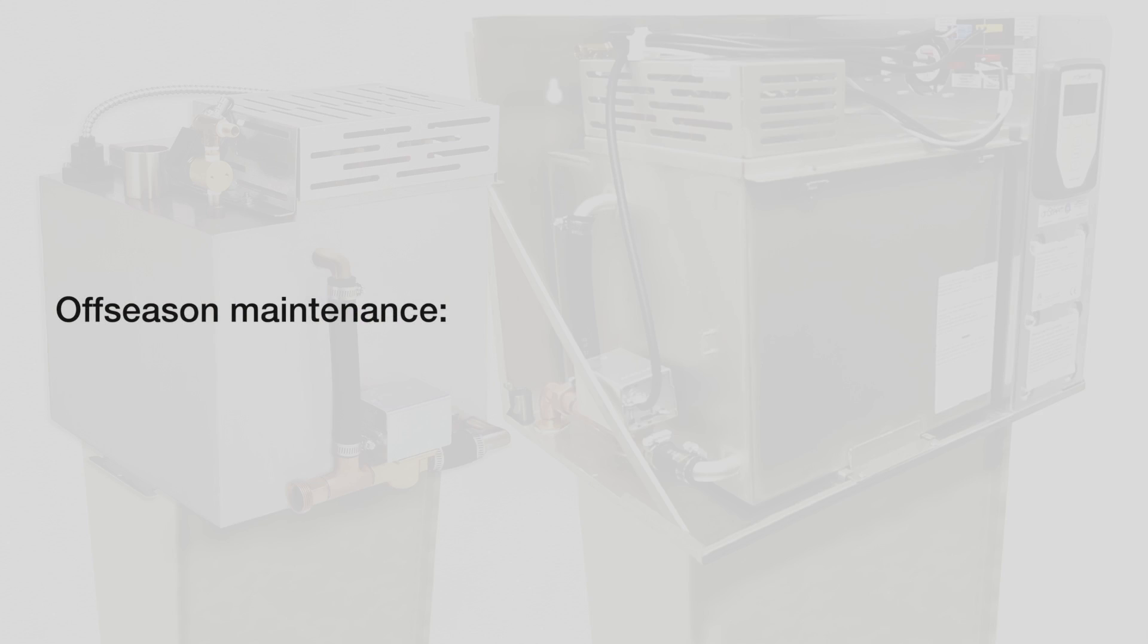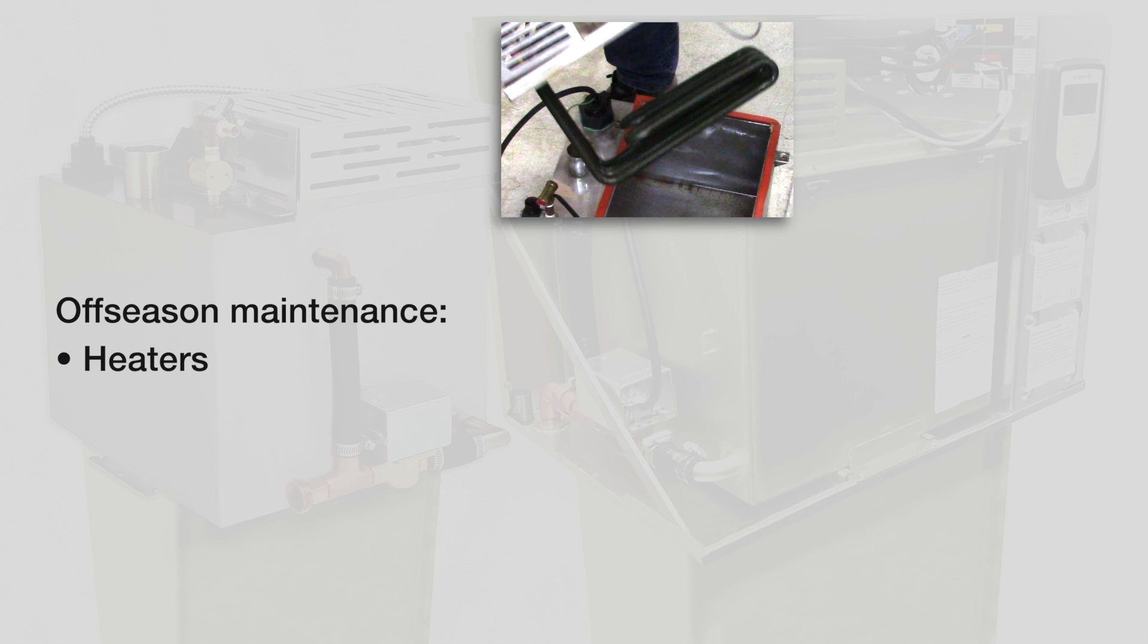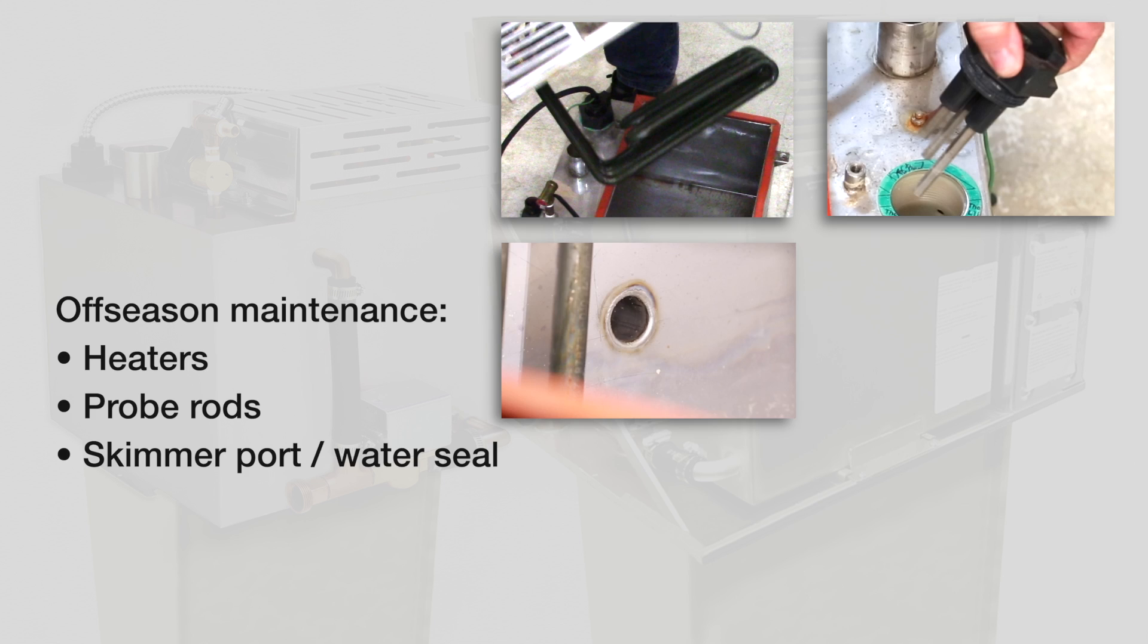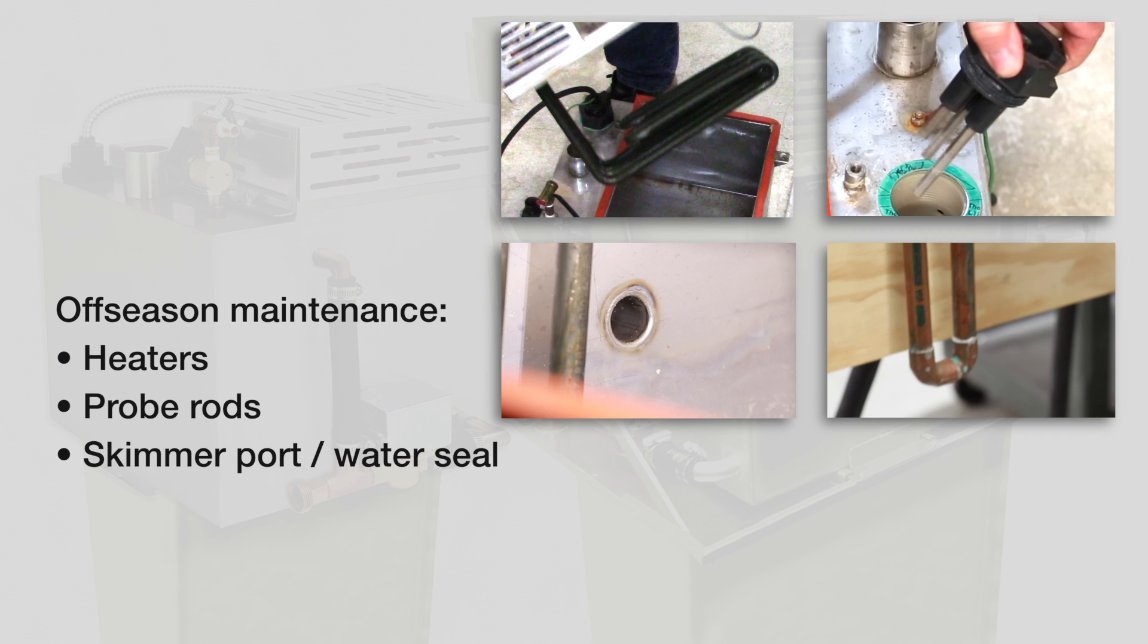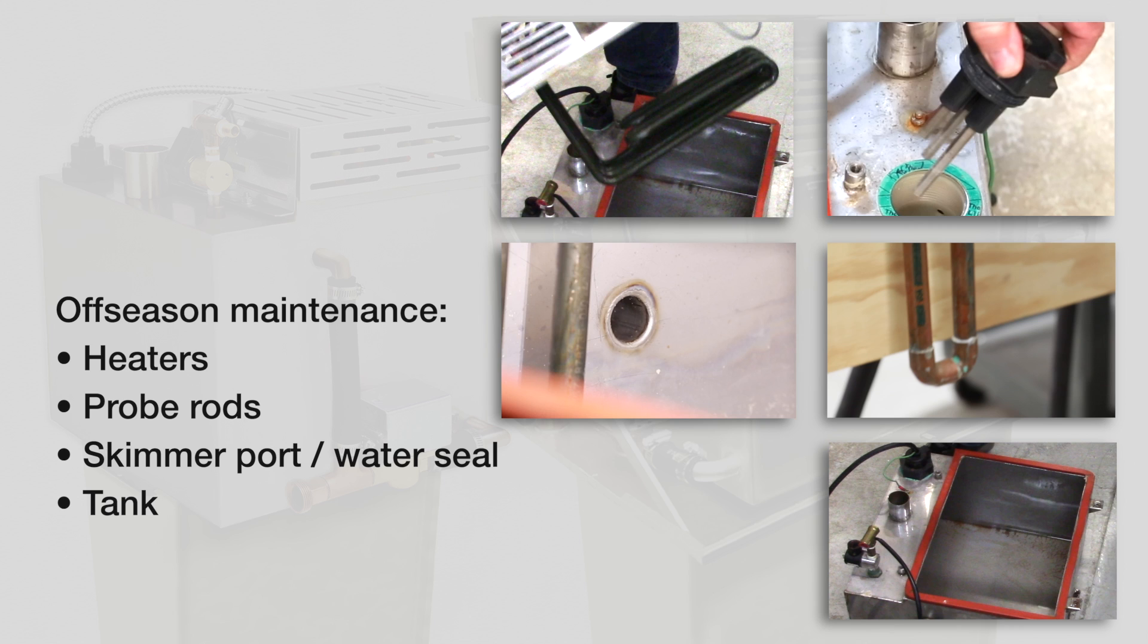For off-season maintenance, perform complete inspection and cleaning of the following: heaters, probe rods, skimmer port and water seal, and humidifier tank. After cleaning, the humidifier should remain powered off and empty until humidification is required.